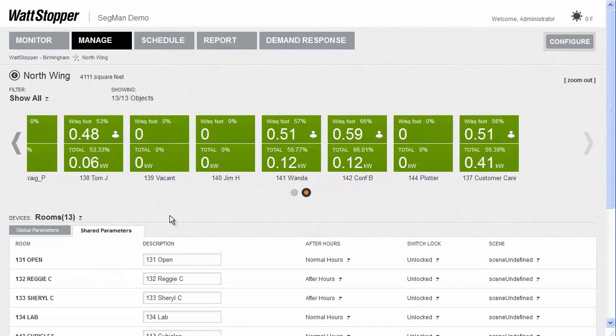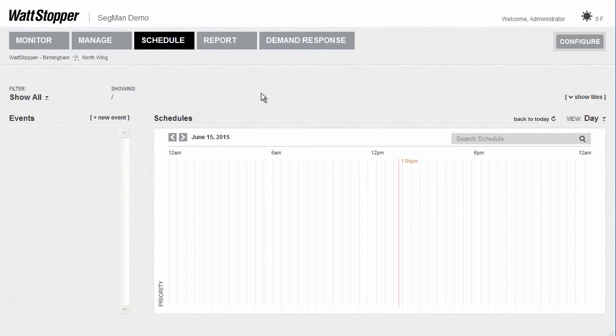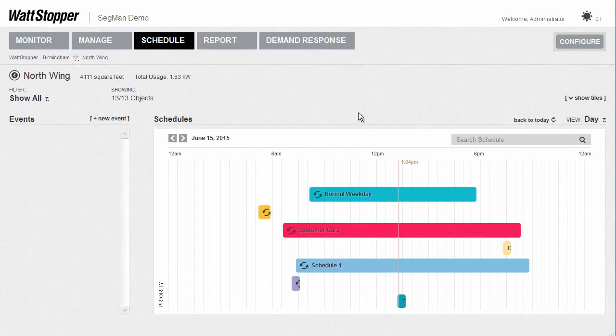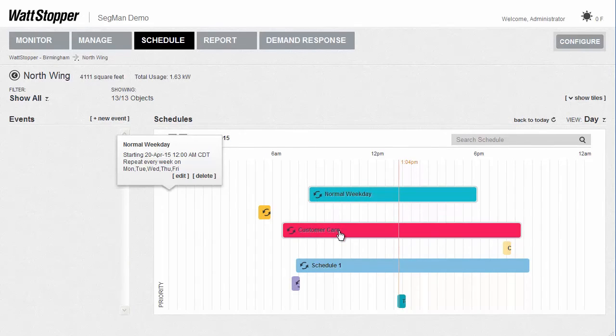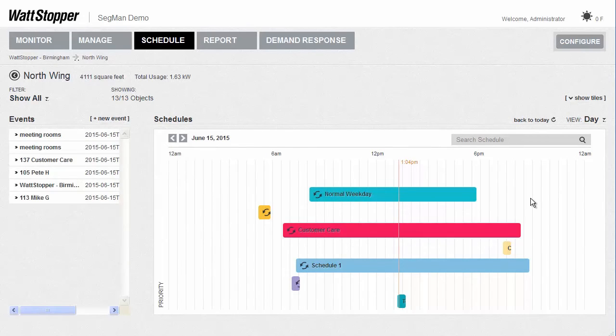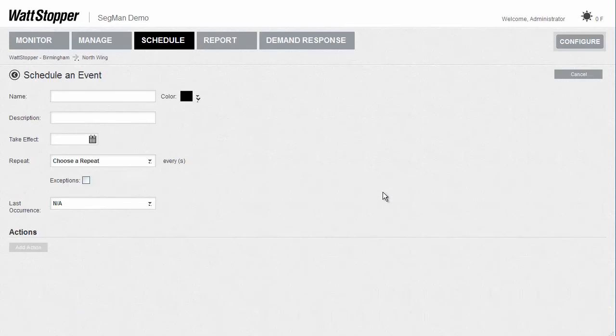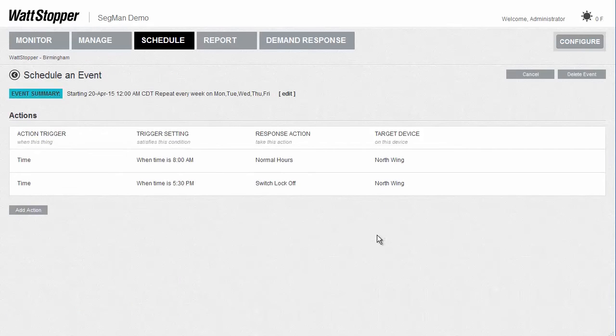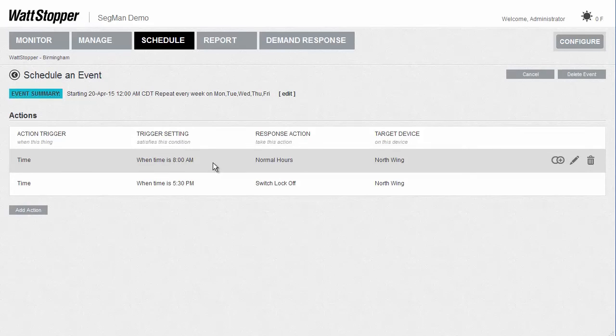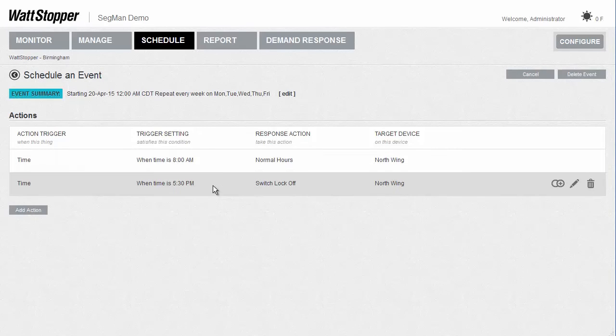You can also use a Segment Manager as a master scheduler for our system. We've completely changed the way information is displayed when a room is scheduled. By default you see a day view, and all groups scheduled on and off, or Normal Hours or After Hours, are now shown as a band. You can change the view to week or month using this drop-down. For this event, at 8 a.m. the SegMan is telling the entire North Wing to go to Normal Hours, and at 5:30 p.m. it's telling the North Wing to go to After Hours.